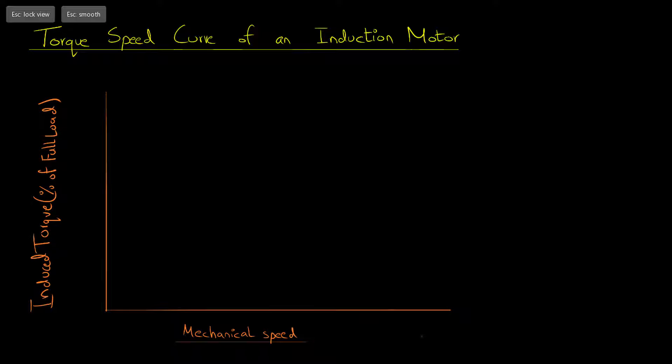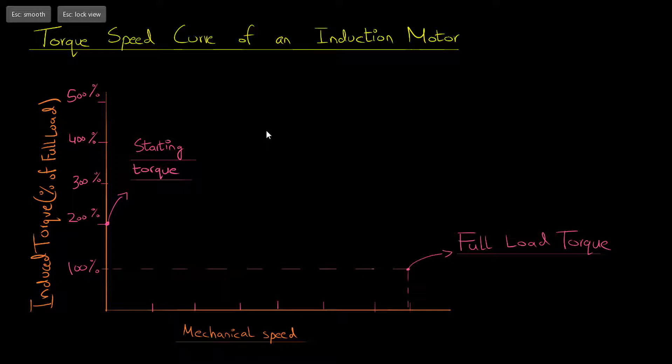Following this curve from the very beginning, we can see that the starting torque of an induction motor is almost 200% of its full load torque, or we can say that the starting torque is slightly greater than the full load torque. This curve increases linearly up to the level of the pullout torque.